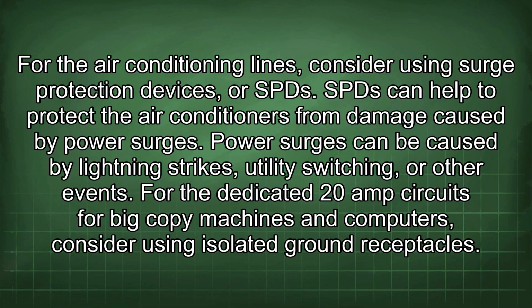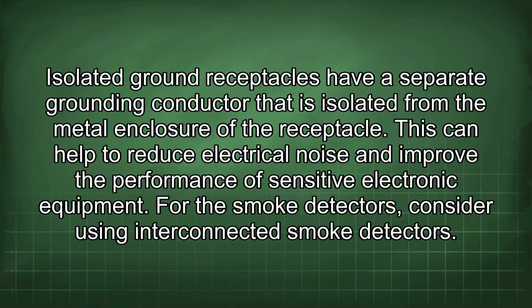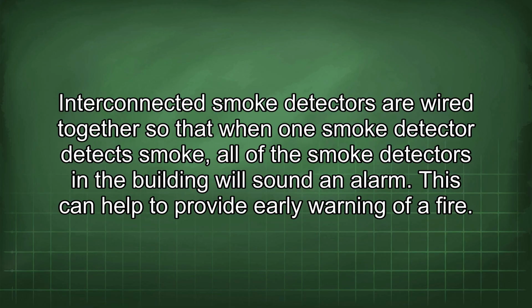For the dedicated 20 amp circuits for big copy machines and computers, consider using isolated ground receptacles. Isolated ground receptacles have a separate grounding conductor that is isolated from the metal enclosure of the receptacle. This can help to reduce electrical noise and improve the performance of sensitive electronic equipment. For the smoke detectors, consider using interconnected smoke detectors. Interconnected smoke detectors are wired together so that when one smoke detector detects smoke, all of the smoke detectors in the building will sound an alarm. This can help to provide early warning of a fire.